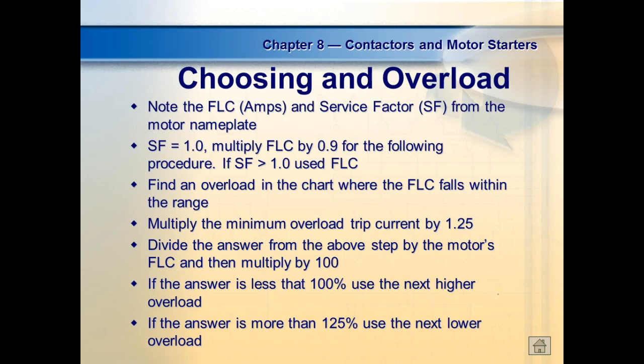Then we'll multiply the minimum overload. If the service factor is one, then we're automatically going to degrade this. This guy here has his overloads set up for a 1.25 service factor. So that's the size he's got out there. That means if it's got a one, we're not going to use 100%, we're going to degrade it to 90%. So we'll multiply it by 0.9, right? That make sense? No? Then tell me what doesn't make sense.